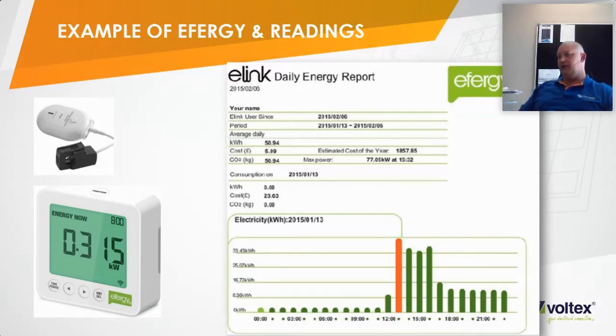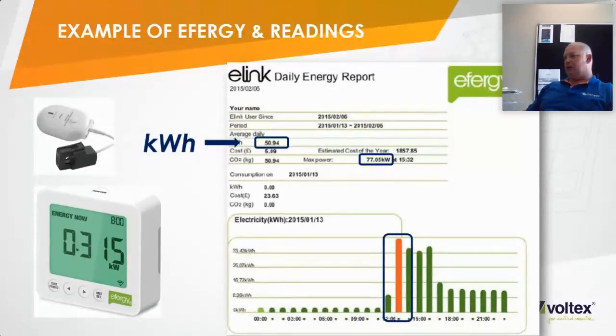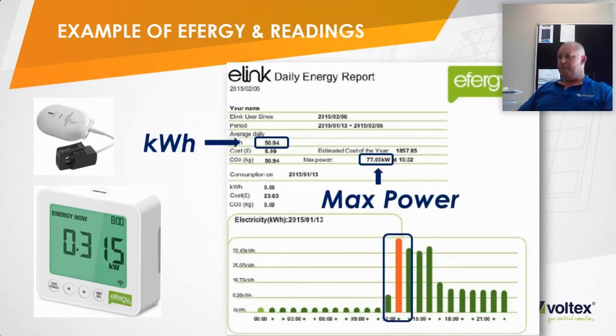It gives you a good indication of what you're consuming at any given time while the unit is installed. And at the end of the day, when we need to do a system design, it gives you the usages that we require. So the first little block is the kilowatt hour. That is what we would use to spec the battery bank according to. The second block would show your peak consumption. This gives us an idea of what size inverter to spec. That's your maximum power.